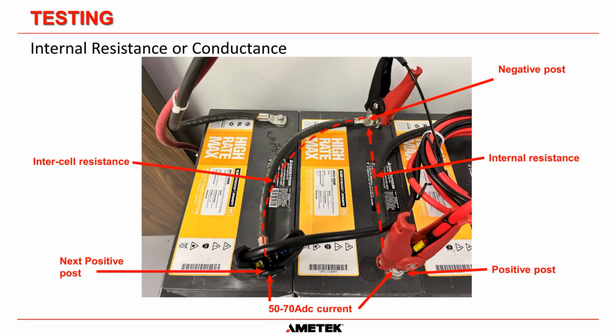Okay. So what's happening in this picture here, when you press the test button, the current or the load is being applied between this terminal here and this terminal here. Okay, so that 70 amps current is going to flow all the way between those two probes. And the reason why we have this red and black probe is this probe and this probe are measuring internal resistance. Okay, and then this probe and this probe are measuring the intercell resistance.